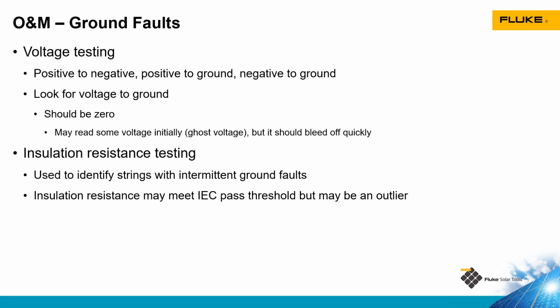An example of that is when I was doing some insulation resistance testing on a low slope commercial roof. All of the strings were exceeding the maximum resistance value of my meter, which was 2 gigaohms, except for one string. It was measuring at about 156 megaohms, which is still way beyond the minimum value for the IEC standard, but it was different than the other strings in that system, which were all basically the same. When I tracked down that string, I found that a module interconnection between two modules was laying in a puddle on the roof. So even though it wasn't a full ground fault, we were still losing some resistance to ground there. As soon as I lifted that out of the puddle, properly affixed it to the racking and let it dry off for a bit, the insulation resistance of that string also exceeded the 2 gigaohm limit of my meter, so it matched all the other circuits in that system.